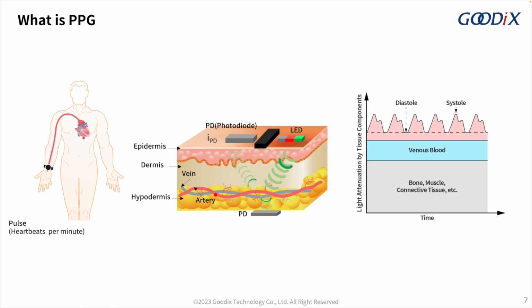The absorption of light by most human tissues is basically constant, which constitutes the DC component of PPG. Since the volume of blood in the artery changes periodically with the contraction and relaxation, the absorption of light also changes accordingly, which constitutes the AC component of PPG. The ratio of AC to DC is called perfusion index, which is the most basic indicator for measuring the quality of the PPG signal. Usually, the transmittance PI can reach 0.2% to 10%, but the reflective PI applied to the wrist is usually much weaker than the transmittance type, so the measurement is more difficult.